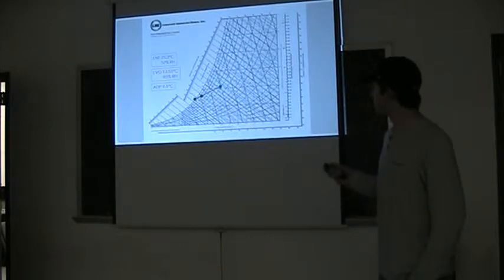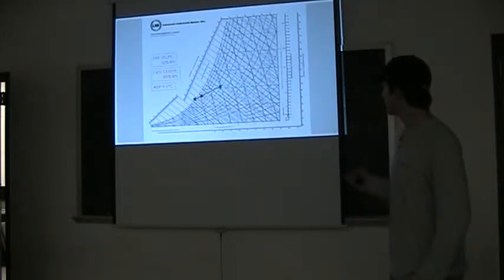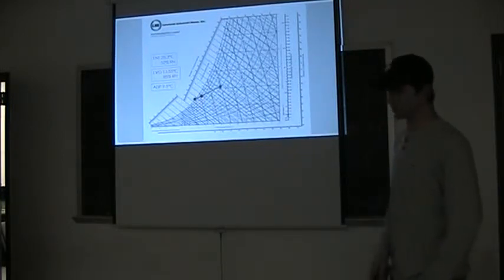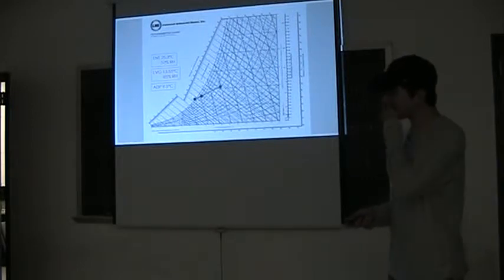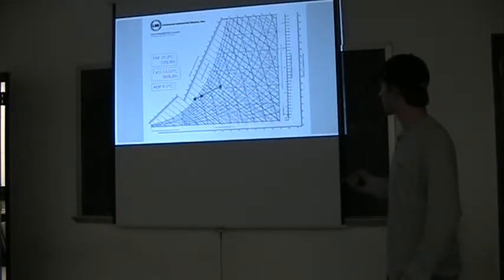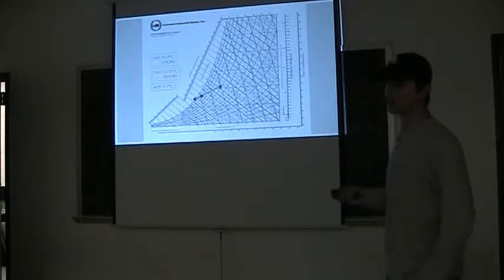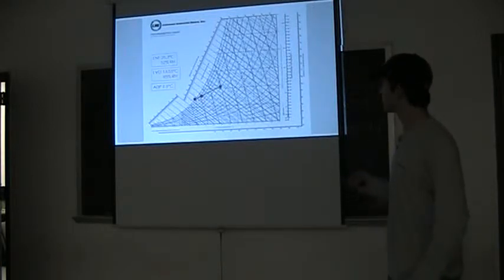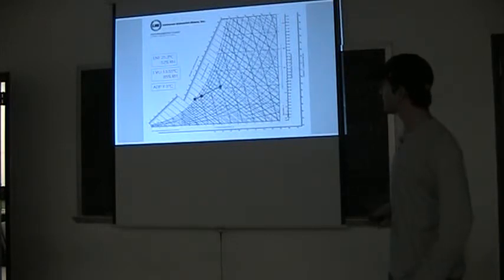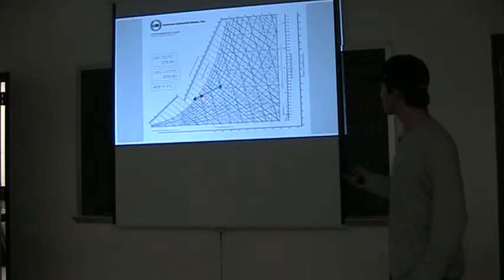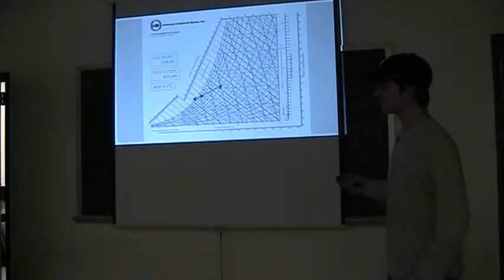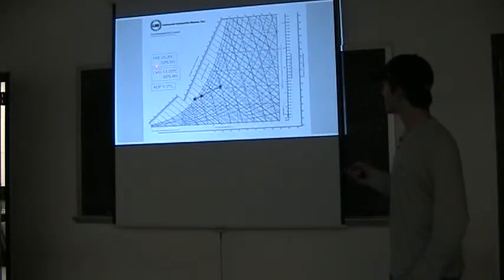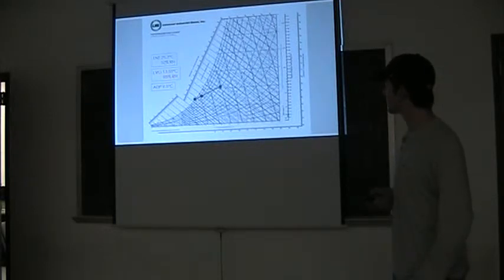This is the coil line. All of the temperature values were put in Celsius to be put on this chart. This blue dot is the inner condition, the room temperature, the room condition. So 52 percent relative humidity and 77.6, so 25.3 degrees Celsius. This leaving condition is just after the little AC unit. So that 56 degrees was put into Celsius, 13.55. That should be 88.5 relative humidity.